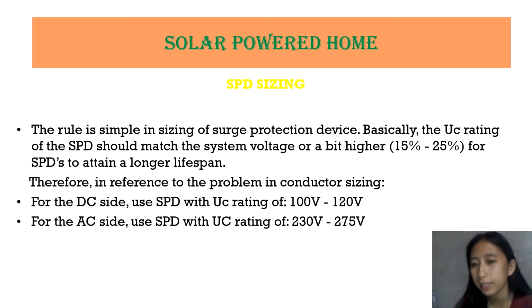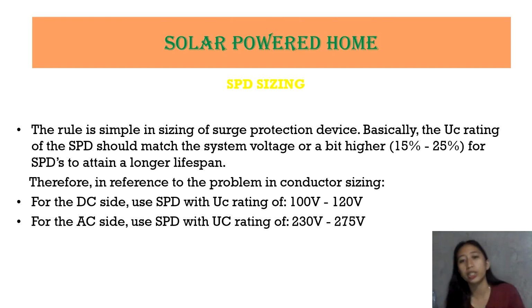Okay, so what are the rules in SPD sizing? The rule is simple in sizing of surge protection device. Basically, the UC rating of the SPD should match the system voltage or a bit higher, 15% to 25%, for SPDs to attain a longer lifespan. So, para daw, mas humaba yung buhay ng ating SPD. Therefore, in reference to the problem in conductor sizing, ano ba yung mga kailangan natin na meron tayong mga reference dito? Para daw sa ating DC side, use SPD with UC rating of 100 volts to 120 volts. So, para naman sa ating AC side, use SPD with UC rating of 230 volts to 275 volts.